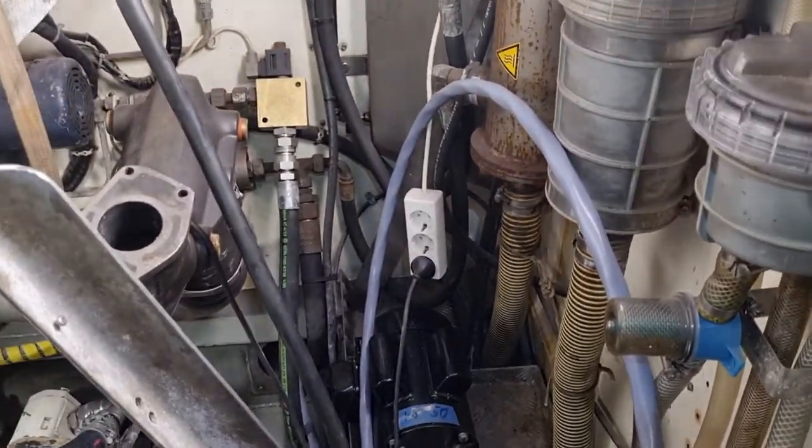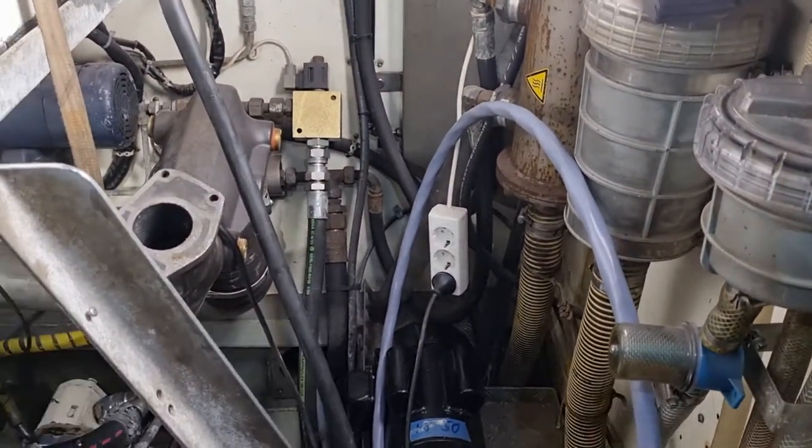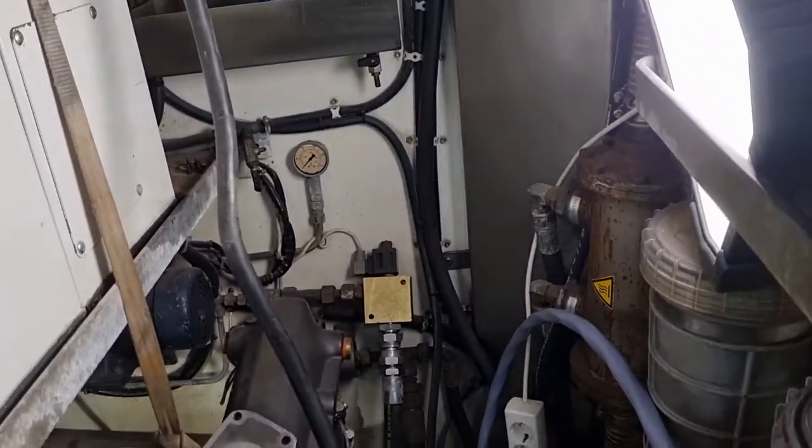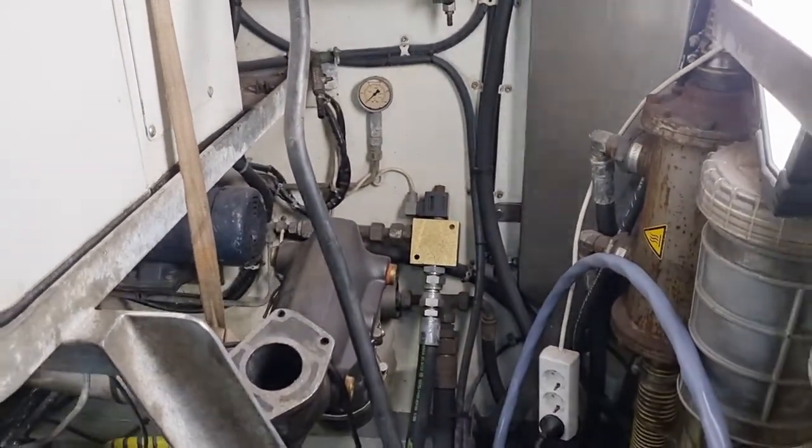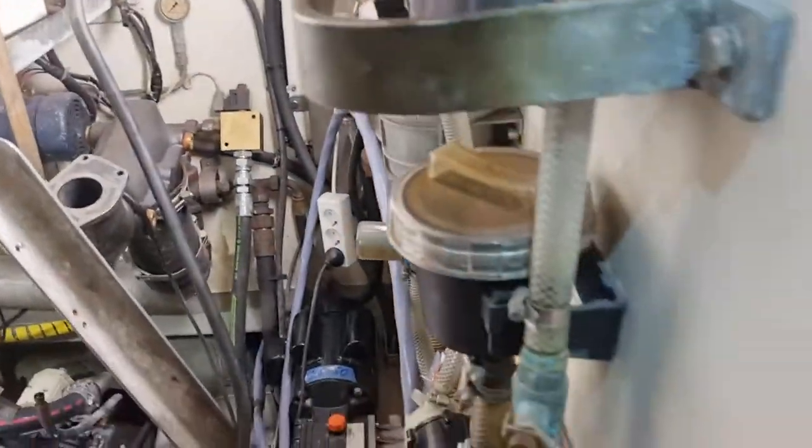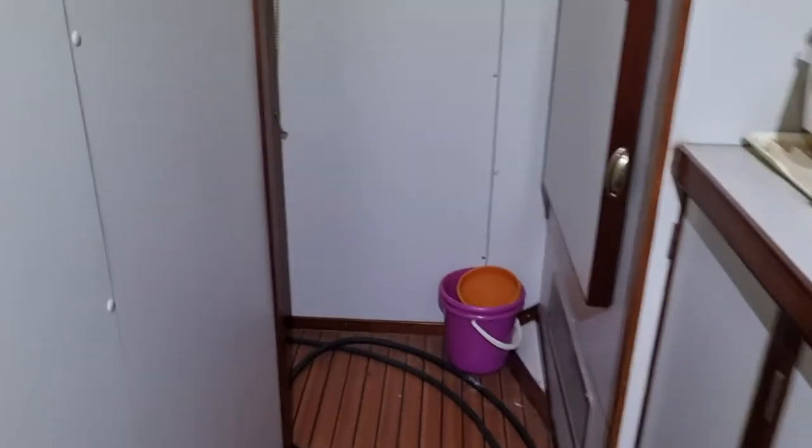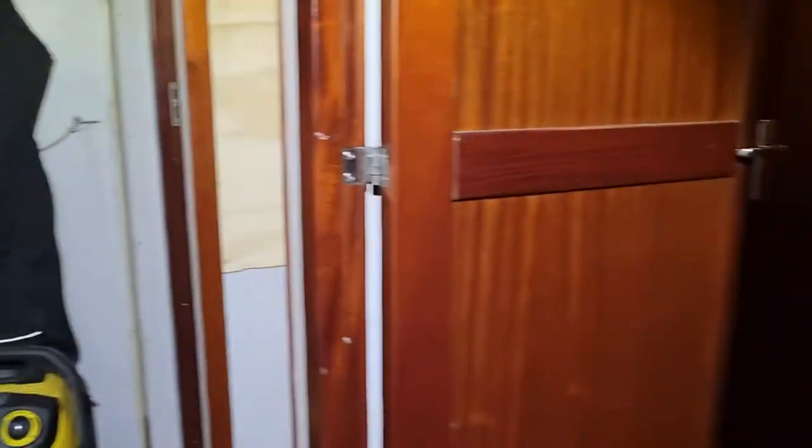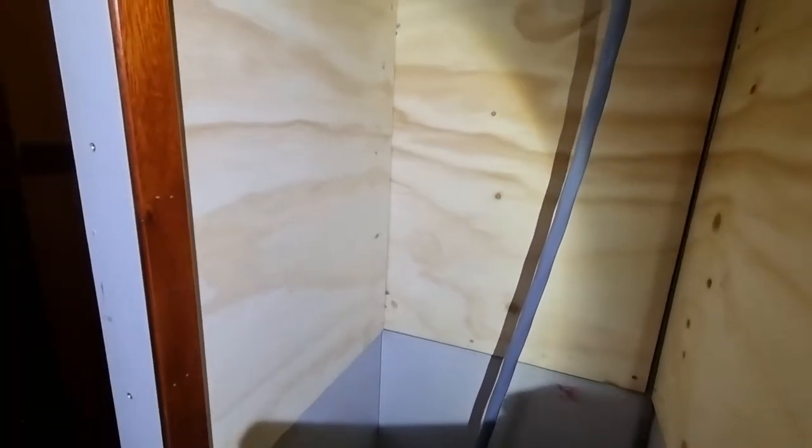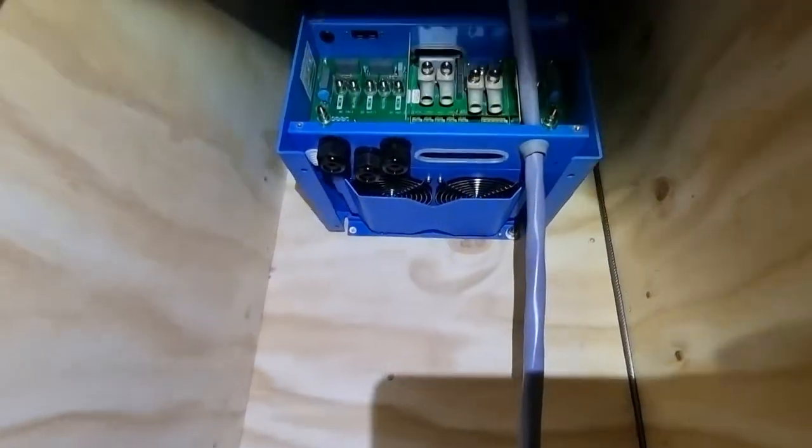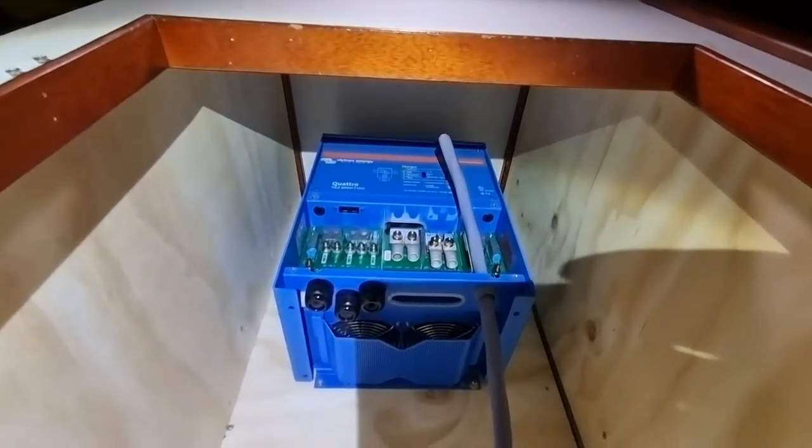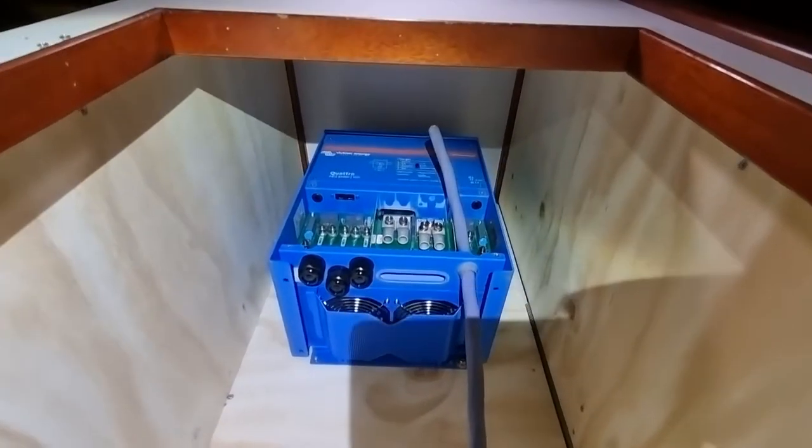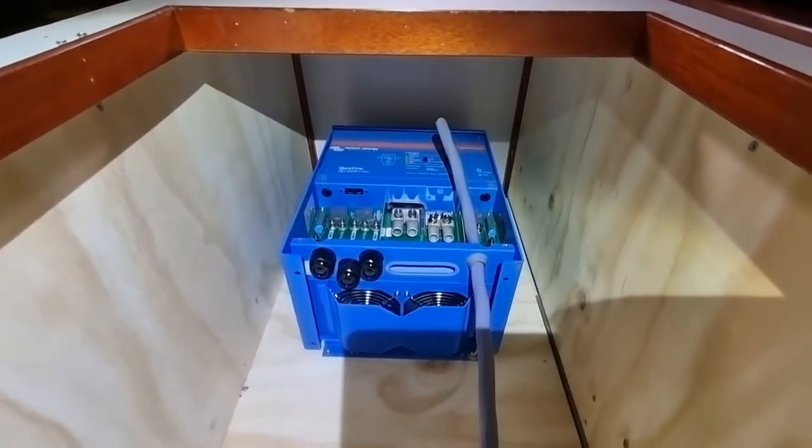Then we can start talking about the new system. The new system will be based on a Victron Quattro 24 voltage 5 kilowatt, and that one is placed not in the machine room anymore but in the cabinet between the two cabins. I turn on wide angle so you see better. It's here in the top of this cabinet. Inside here I will now install most of the electronics.